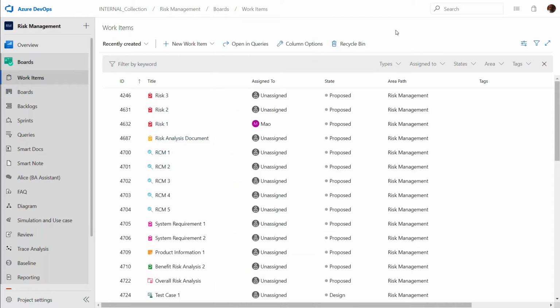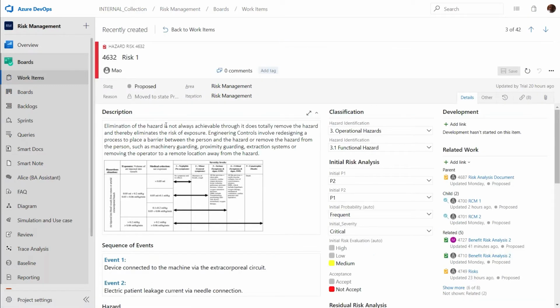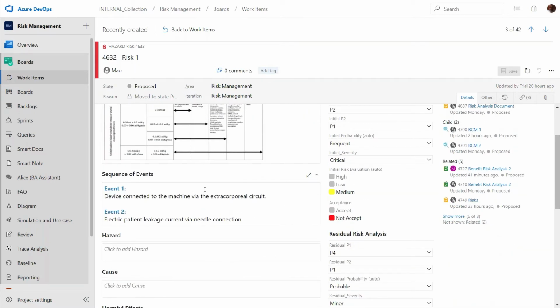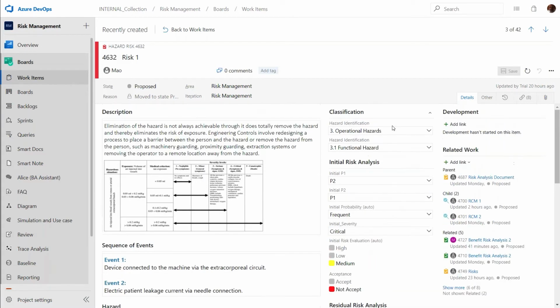And now I'm going to show you a risk analysis workflow. And starting from there, how can we document, review, report, and baseline, and also check the completeness of your analysis, all in Modern Requirements? We know that there's a strong connection between your device's design input and the risk management. Once you know how the product is intended to be used, you can start to identify the potential source of hazards.